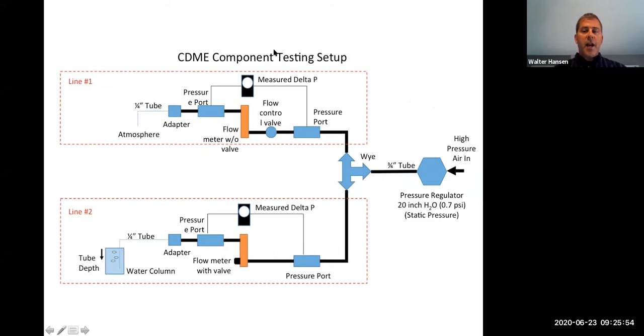Starting on the right side, we supplied high pressure air from an electric powered compressor, then put it through a precision low pressure regulator to simulate the actual pressure range coming from a ventilator. We split the outlet of the regulator into two lines and ran them through our various meter and valve combinations. We put the outlet of one line into a water column to create back pressure, simulating a patient with lower lung compliance. Using that setup, we measured the pressure drop across each component using a digital pressure meter, and verified our ability to control the flow rate in each line independently, even when one line had back pressure from the water column and the other didn't. That was a good sign.